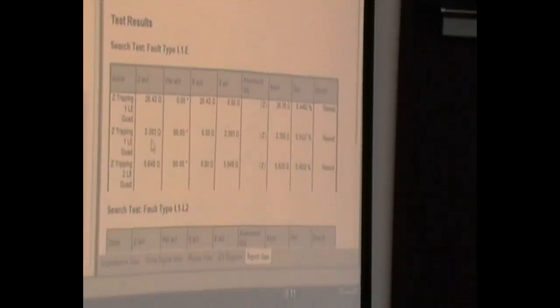What was the first fault? Line to earth. Now the actual, what you want, you already have your setting, you want only the actual. What was the resistance? First test, am I expecting the resistance for phase fault? No, it's earth. So basically it's 26. What was the resistance for zone 1? Zone 2 is the same, by the way. What was the setting? 26.3. What is the relay pickup? 26.42. Almost the same. And the reactance was 2.38, now it's 2.39.